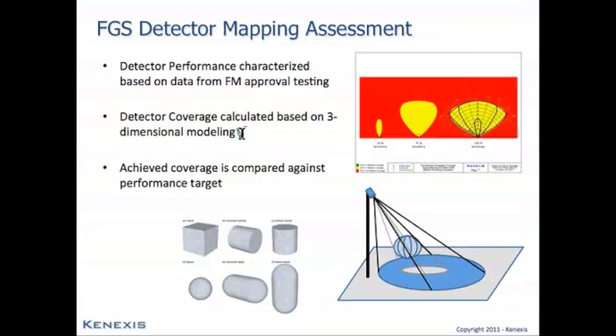Okay, so the detector coverage is going to be calculated based on three-dimensional modeling. Essentially, analytical geometry is going to be used. The cone of vision is essentially a cone, and the intersection of a cone with a plane is the realm of conic sections. So the conic sections that are generated when a plane intersects a cone can be used to generate the footprint, if you will, of the cone of vision on the elevation of interest. And this needs to be done fully in 3 dimensions.